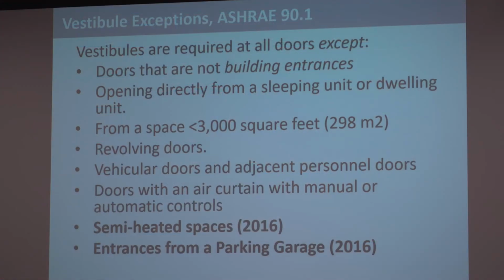ASHRAE also has some vestibule exceptions. They're very similar to IECC, but if you're following one path or the other, you've got some slightly different requirements. The only additional requirements, the ones in bold, are new in 2016: semi-heated spaces. Actually, I didn't mention this. ASHRAE has a third conditioning category for semi-heated. It's always been in the code. It has different envelope requirements. I'm also not going to talk about those envelope requirements because it adds a whole other layer of complexity, and semi-heated are less common conditions. So I'm just trying to cover as much of the common conditions as possible.